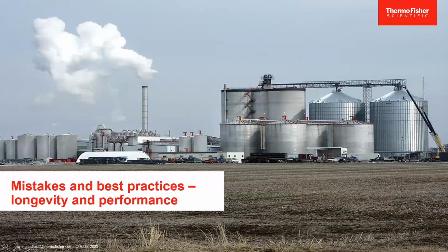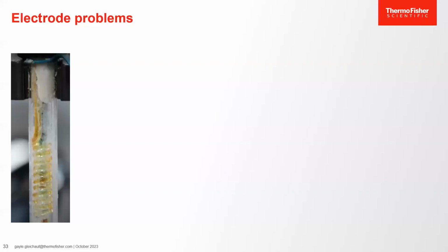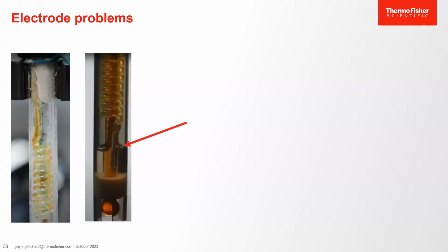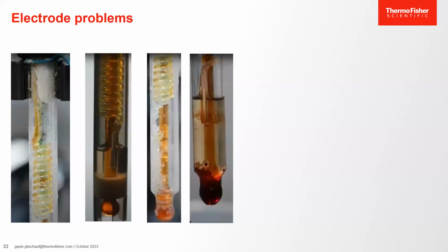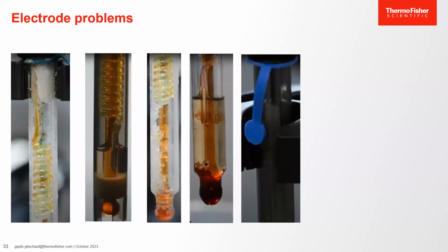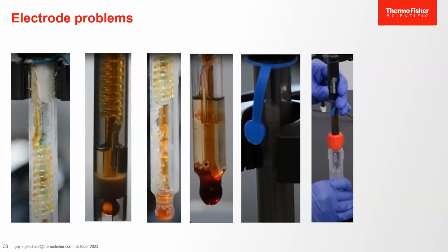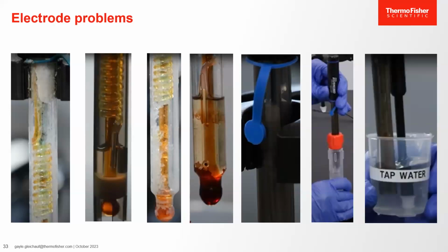All right, so our final segment of this presentation is this: mistakes and best practices for longevity and good performance of our pH measurement system. Have you seen pH electrode problems in your lab? I have. For example, the fill solution is dried out and turned to crystals inside the electrode. There's very little fill solution left in the electrode. The electrode bulb has dried out or is coated and dirty. The fill hole is covered while the electrode is being used to make measurements. Wrestling with an electrode to get it into or out of a storage bottle, or rinsing with water that's not clean and purified.